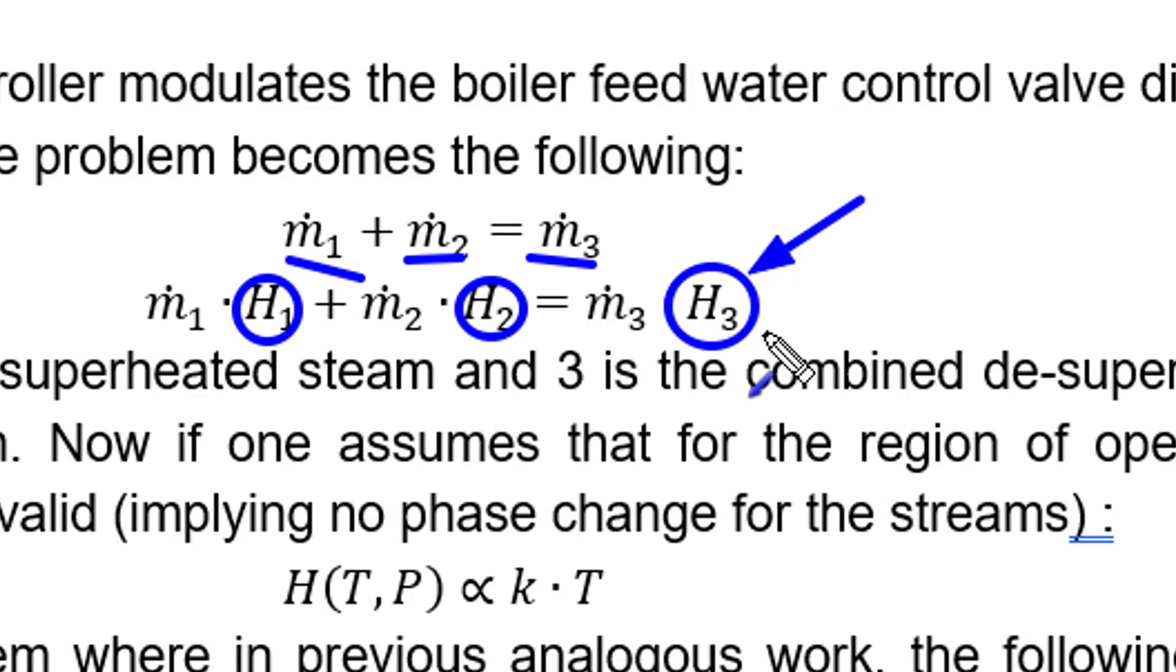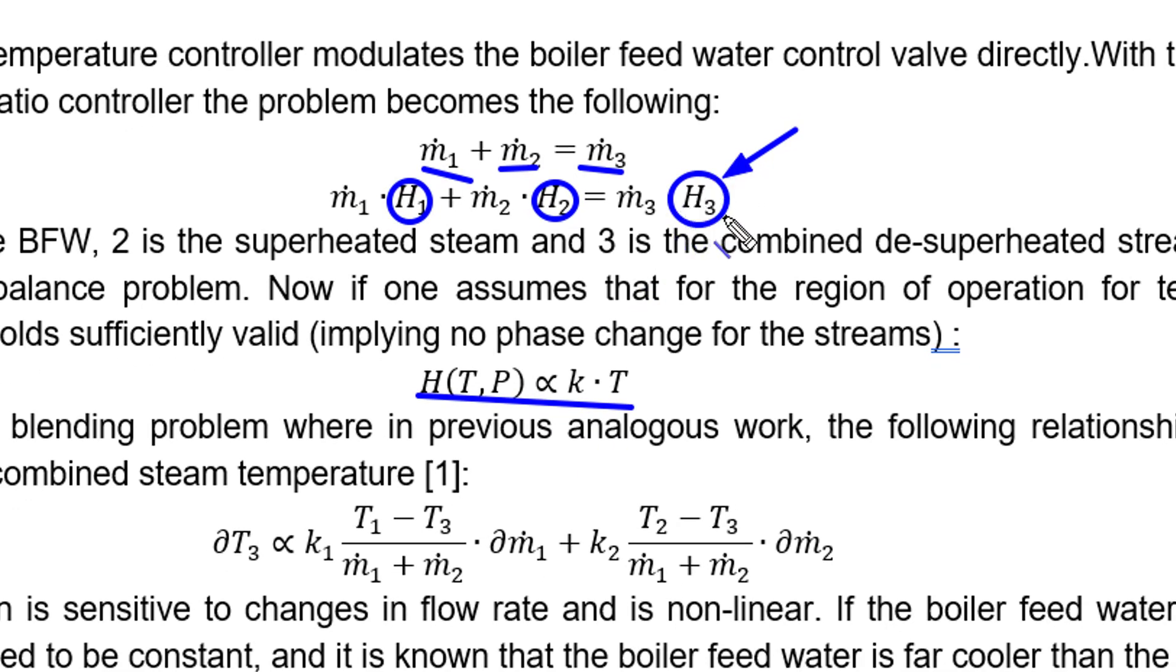If you plot the enthalpy of steam around the typical operating region, you'll find that enthalpy as a function of temperature and pressure is mostly linear. It's actually a quadratic but fairly linear to temperature. We make this assumption and replace every enthalpy with k·T. We change the subject of the equation because we're trying to control temperature, which is linked to quality.